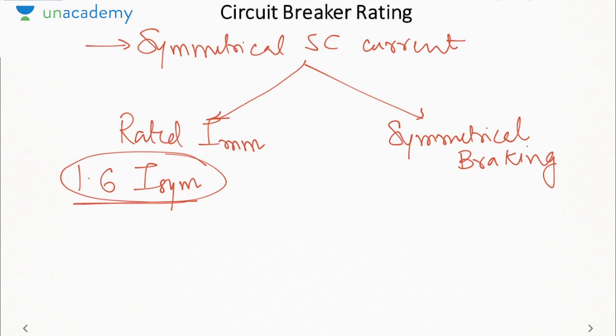Now why have we multiplied it by a factor of 1.6? Because the symmetrical short circuit current contains only the AC component. It does not consider any DC current. Now instead of simplifying the DC current using exponentials and all, we are taking an estimate of the DC current, that is 0.6 times the AC current. Hence the total current will become 1.6 times the symmetrical short circuit current. So instead of calculating the transient current, we are multiplying the whole current by an empirical factor to account for the DC offset current.